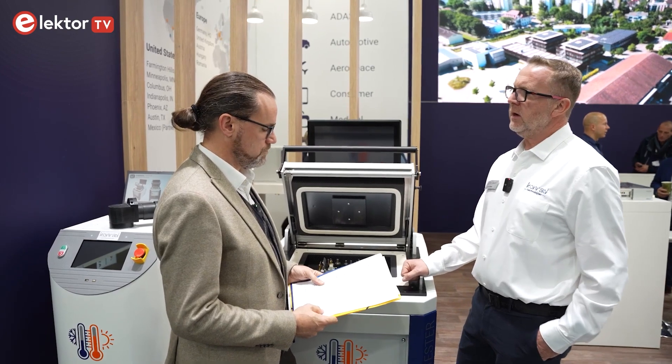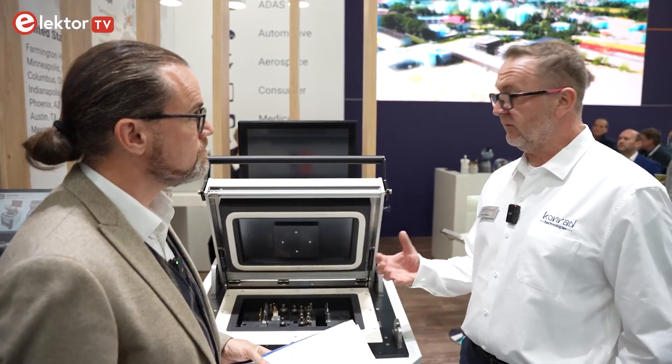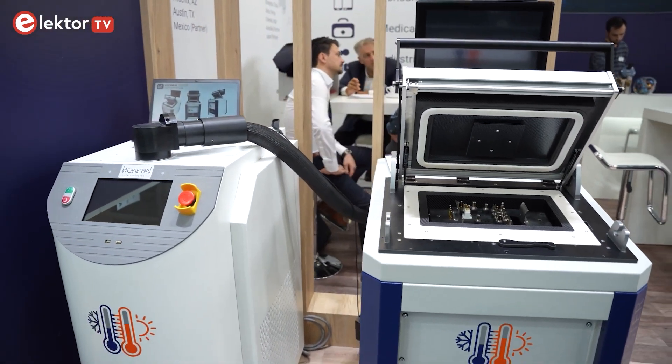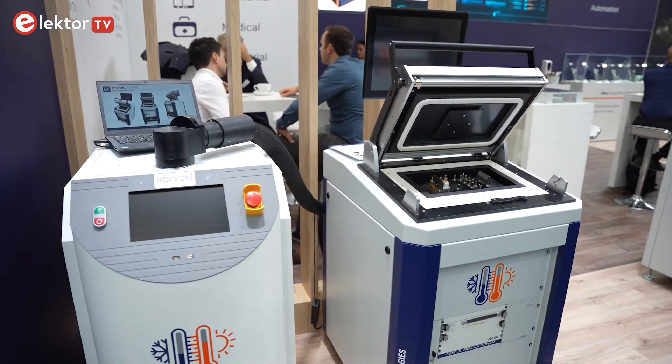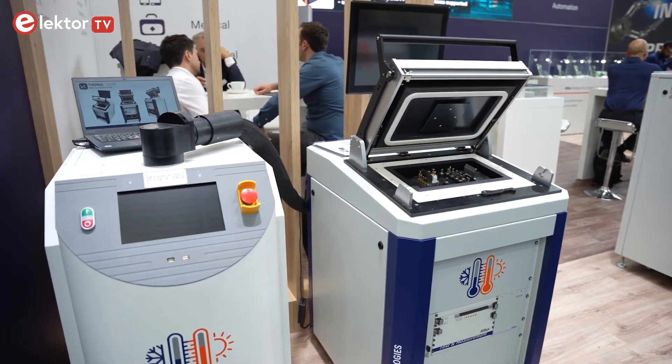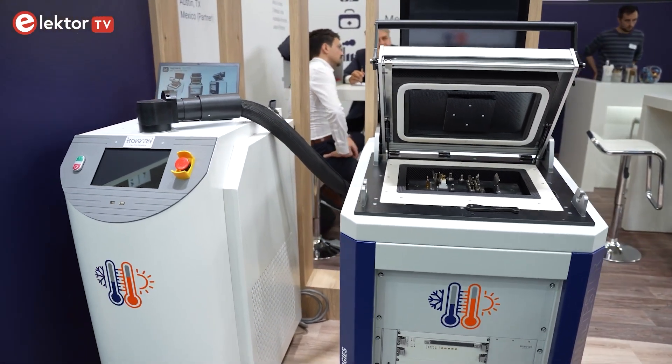Konrad Technologies takes a different approach to environmental testing — not just checking whether the device runs via power and bus communication. Testing is done at PCB level, with access to all test pads on the device, so you can measure not only whether it's running, but also the full behavior of the unit under test.